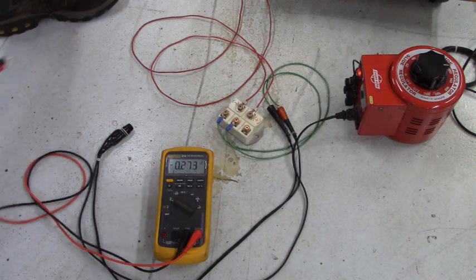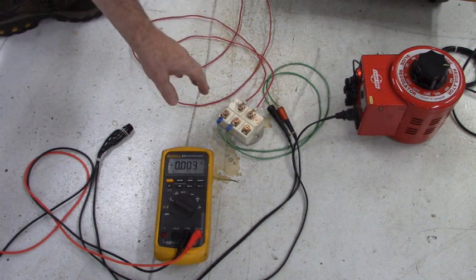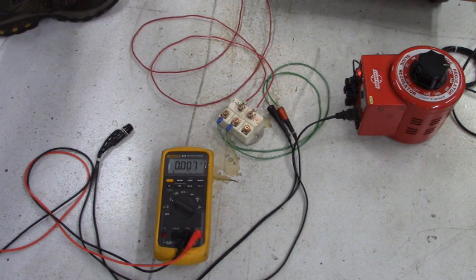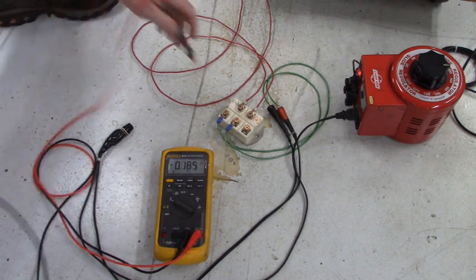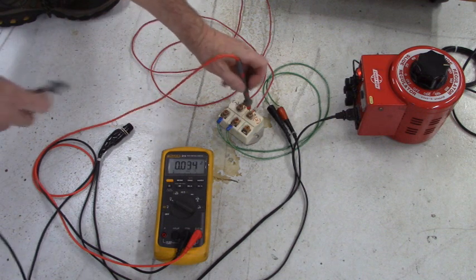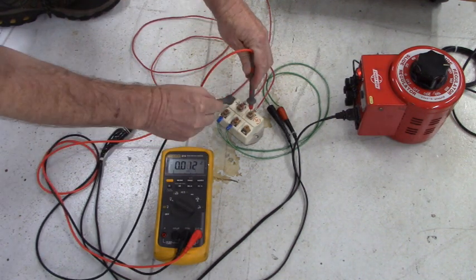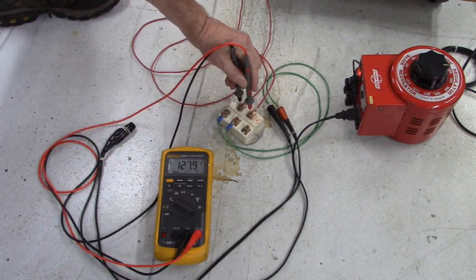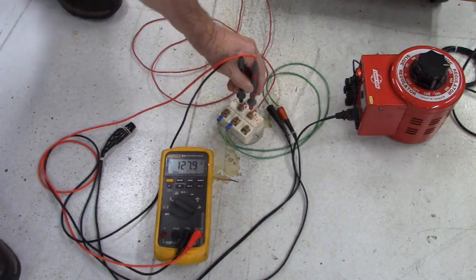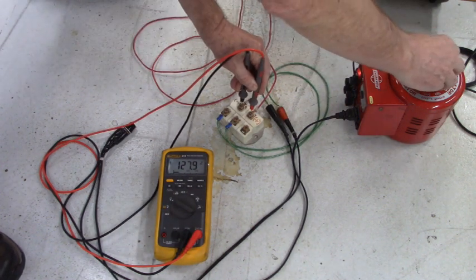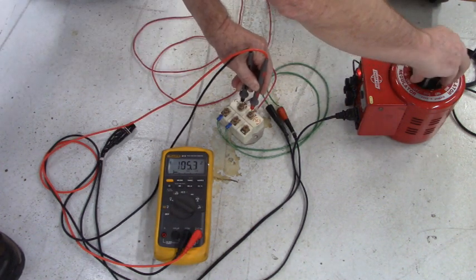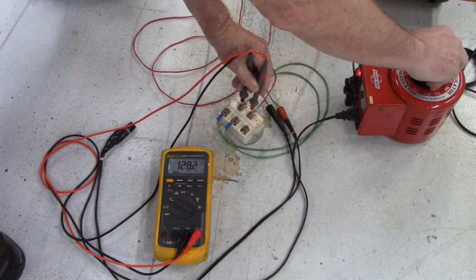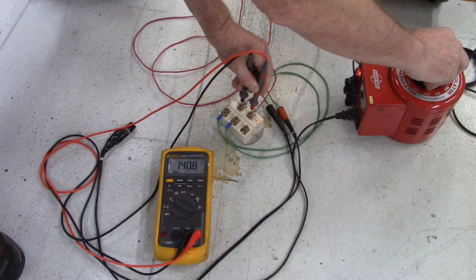Now that we have our connections of the bridge rectifier to the fields, white and green wire, I put my red lead on plus of the bridge rectifier, black lead on minus of the bridge rectifier, and I'm going to increase the variac until we have 150 volts DC.